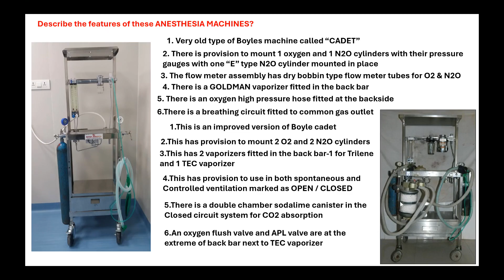Okay, and so we come to a still more improved version here. You have the central pipeline connection as well as cylinder provisions. And you can see these are all the modern vaporizers. And still this has got only flowmeters for two gases, oxygen and nitrous oxide. But what is the difference? In the earlier machine, we had the pressure gauge right over here at the hanger yoke assembly itself, just proximal to the cylinder attachment. But here what has happened?